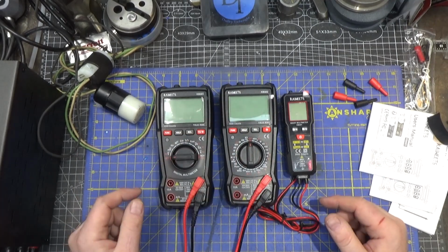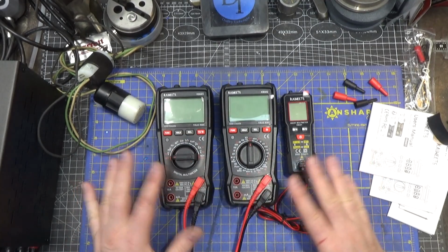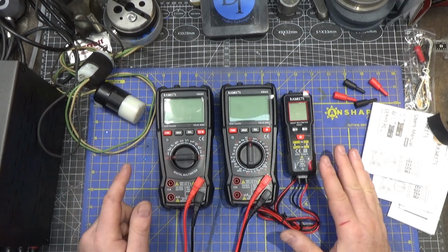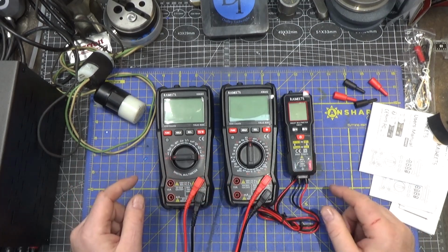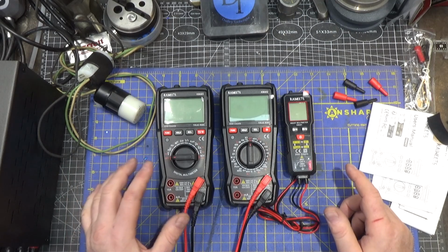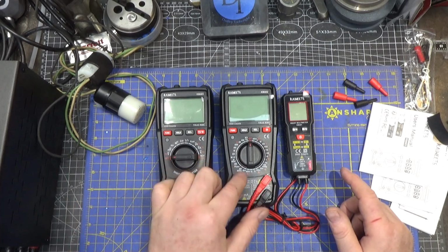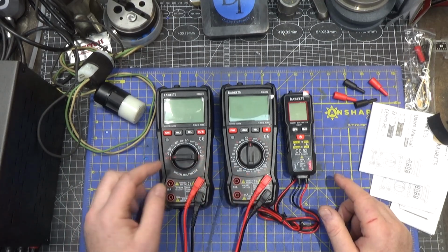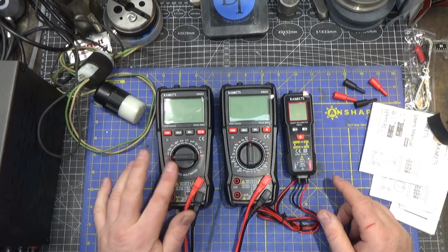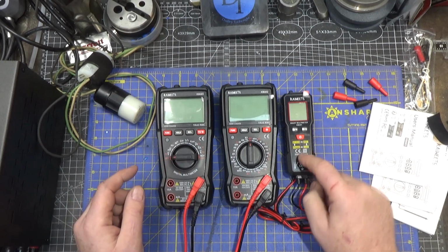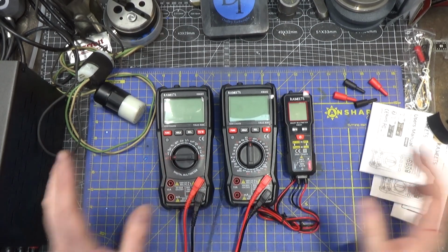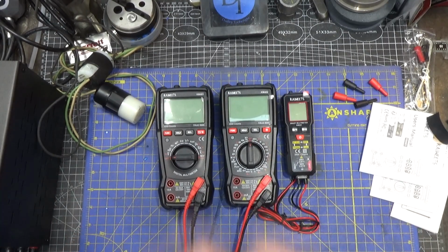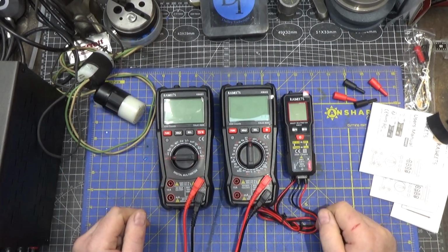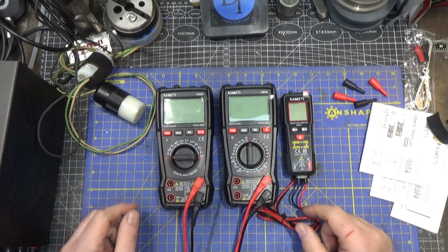Only this one worked at all. I wouldn't trust the non-contact voltage on any of these. If I was going to put my hand on that circuit, I would get the probes on there to make sure. I think you should do the same for sure. This one was pretty reliable on the non-contact voltage. This one was okay, and this one was pretty good as well. But again, maybe that's just a rough indication, so get your probes on there to double check before you do anything involving the circuit.